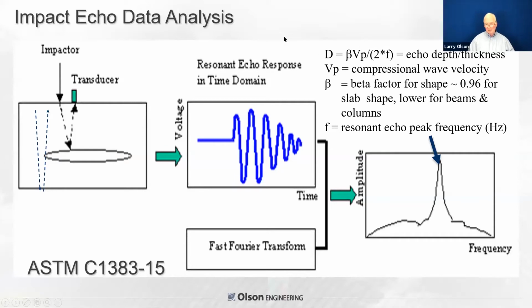So the basics of impact echo, it's a fairly well-known test. As you can see, a full thickness echo goes down and back, those sound waves resonantly reflecting back and forth, or reflecting from a void or open crack at some depth. So you get a time domain signal in which you can sort of see the resonant echoes, but that's not clear. You actually process it with what's called a fast Fourier transform, the FFT. It turns out to have a resonant echo peak.